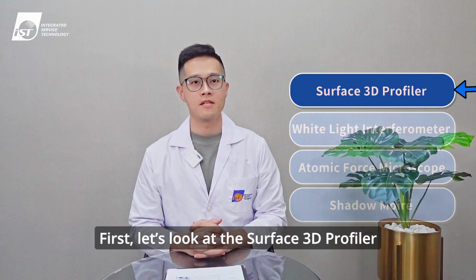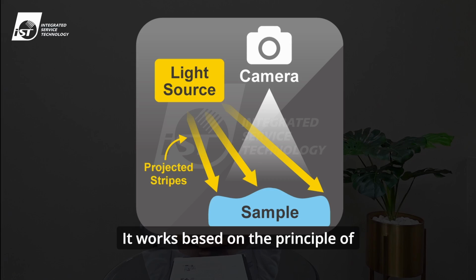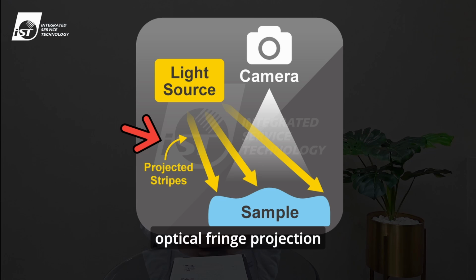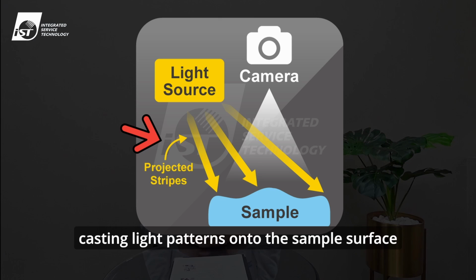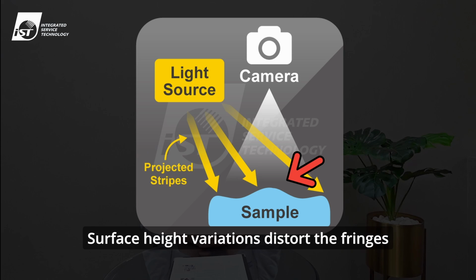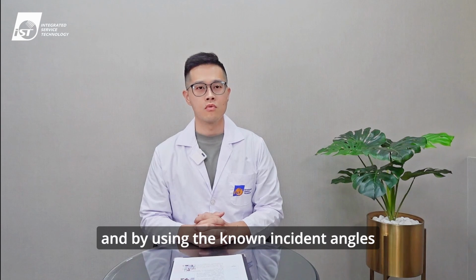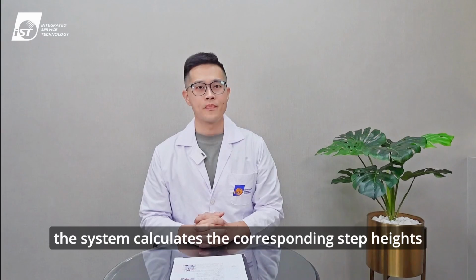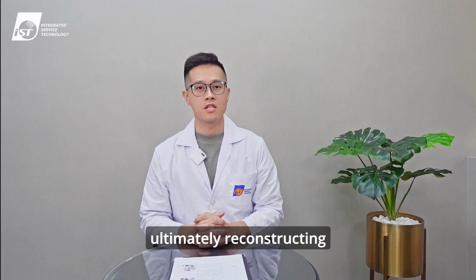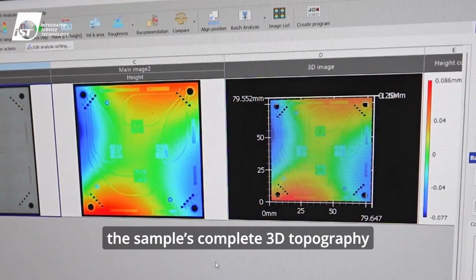First, let's look at the Surface 3D Profiler. It works based on the principle of optical fringe projection, casting light patterns onto the sample surface. Surface height variations distort the fringes, and by using the known incident angles, the system calculates the corresponding step heights, ultimately reconstructing the sample's complete 3D topography.